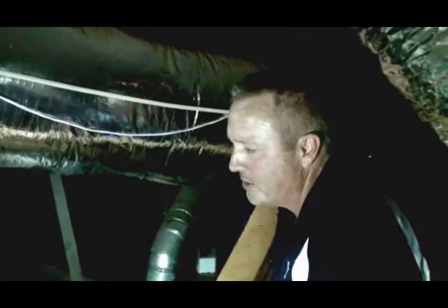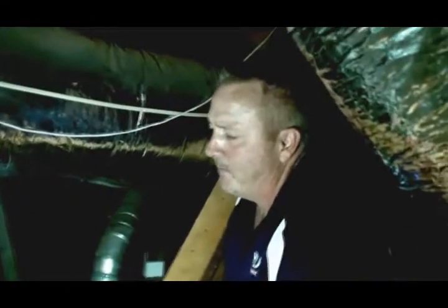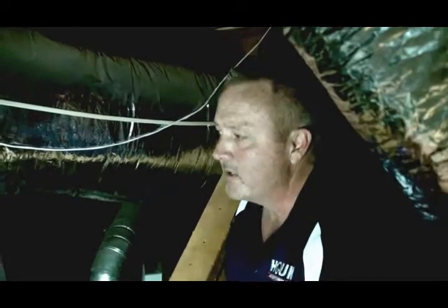For instance, in this particular case, this contractor used a duct board or fiberboard type plenum or box that distributes the airflow. There's a lot of leakage around here where the ducts connect. All that's going to be sealed with a mastic type of sealant that will adhere to the duct system and harden like concrete and won't be affected by the heat of the attic.